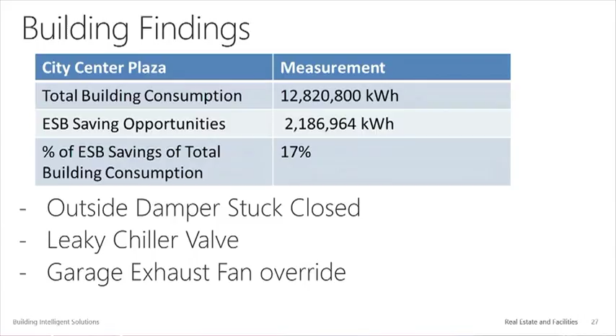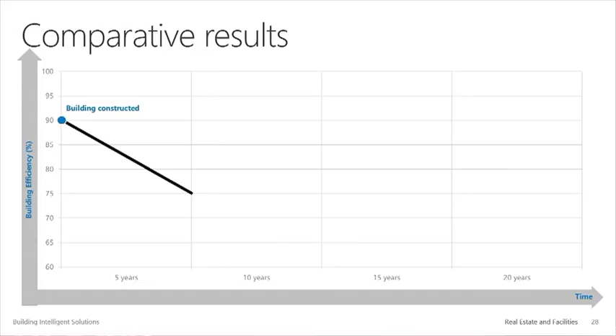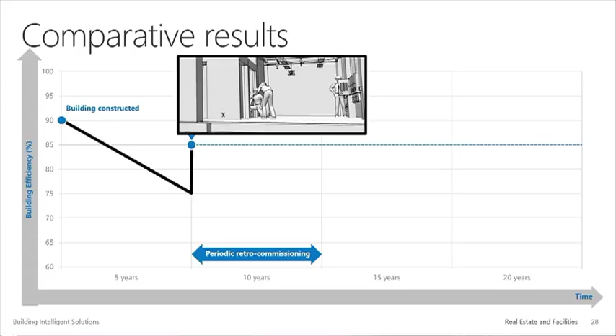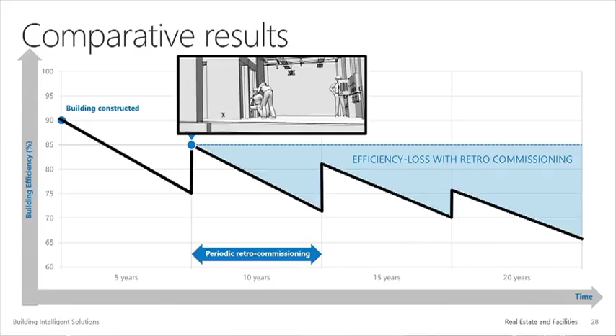So how did I sell this? We retro-commission, or tune, every building across our campus once every 5 years. So we get a building in, we run it for 5 years, and we come back and snap it back up. But we only address the large equipment. So we get to about 20% of the campus each year, about 200 assets, the large assets, and save $250,000 in energy.